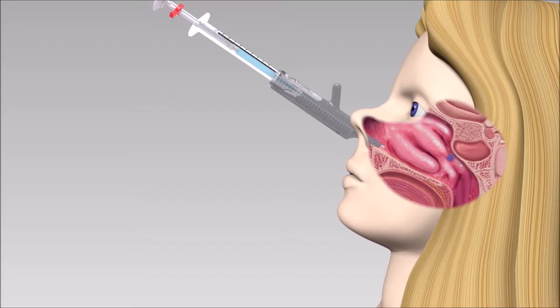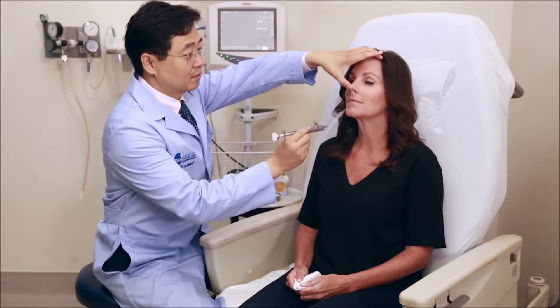Don't worry, the narrow front portion of the TX360 device will not reach the cribriform plate. The wider back portion of the TX360 applicator will limit how far it can be inserted into the patient's nose.